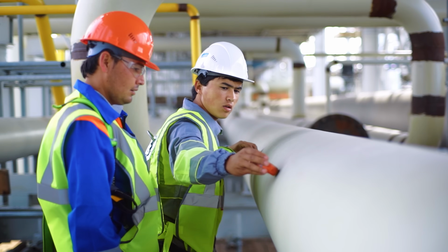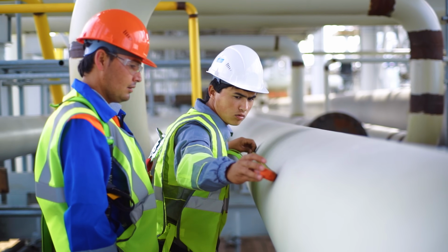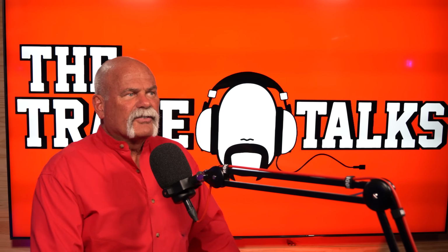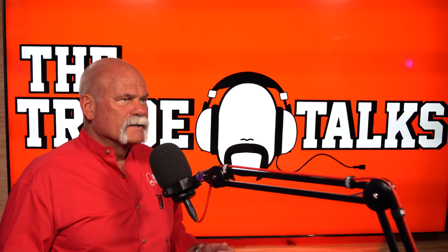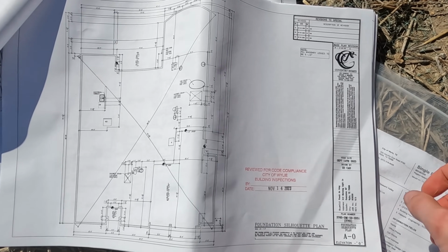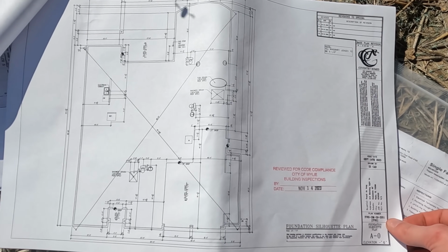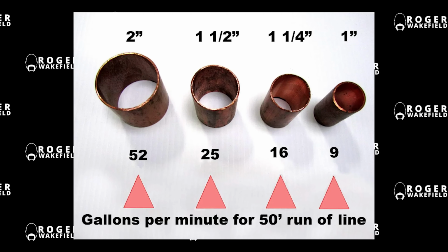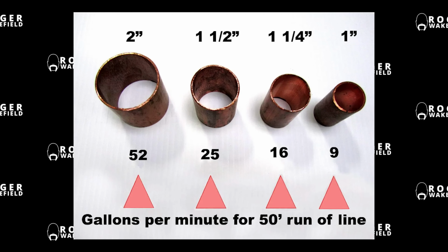Number three, incorrect pipe size for drains. Using pipes that are too small can lead to slow drainage and increased clogs. Drain pipes must be sized correctly to handle the flow from fixtures. Now, when you're first getting into this, you're going to use that formula. You're going to look at the chart to see how many fixture units you're trying to drain, how big the pipe needs to be, different things like that. So you want to make sure that you never undersize your drain pipes. It's going to lead to problems down the road. And if your inspectors are doing things right, you're not going to pass inspection to begin with.